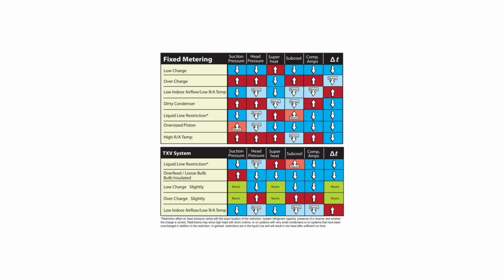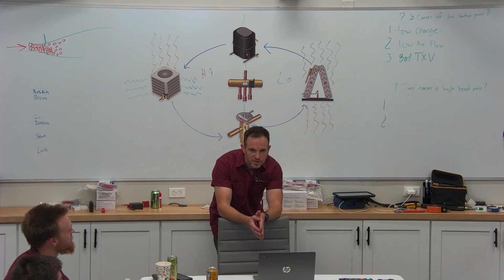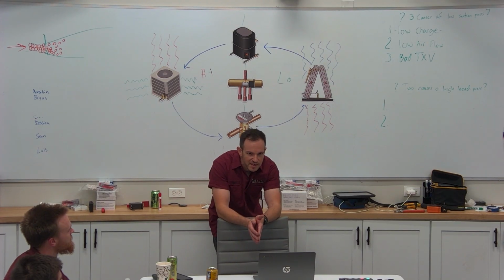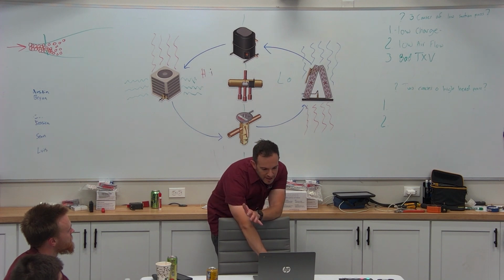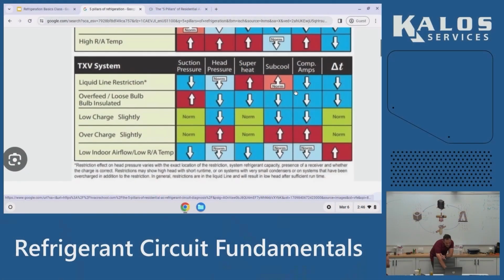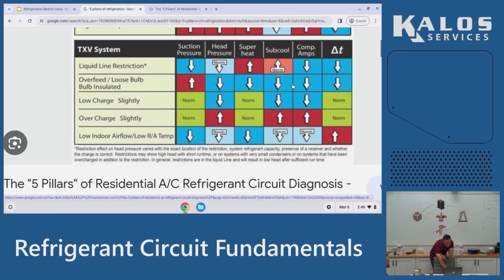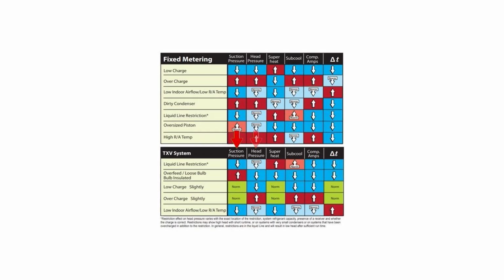I just Googled 5 pillars of refrigeration, and this chart comes up on the HVAC School. I've seen laminated copies of this in some of the vans. It's a really good tool if you're just starting out and trying to do a diagnostic. This chart has fixed metering, but this is the one for the TXVs that we use. These are the 5 pillars: I've got suction, head, superheat, subcool. I really don't care about compressor amps, but I do care about my delta T.